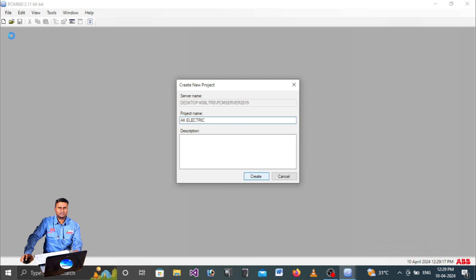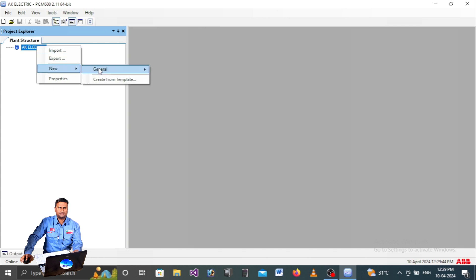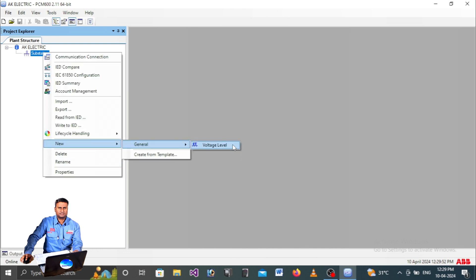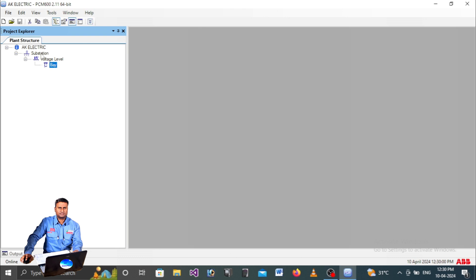A plant structure will open for creating the project file, as is typical in ABB software. Once your project name is established, right-click and go to New > General > Substation. Then right-click on Substation and go to New > General > Voltage Level. Next, right-click Voltage Level and go to New > General > Bay. You can rename each item - for example, type 'Substation 100' for your substation.